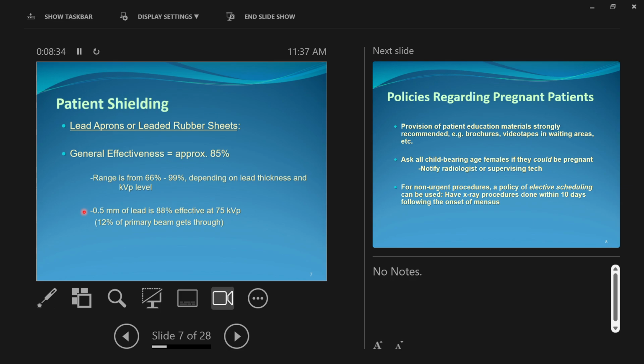Your shields are not likely going to be actually made of lead. Now they can be, but lead is expensive, it's easy to damage, it's very heavy, right? So often the shields are made with what's called lead equivalent. They just have other material that is equivalent in its attenuation, its X-ray stopping properties, but it's not the same type of thing. It's just a different material that absorbs X-rays just as well. So we call it lead equivalent.